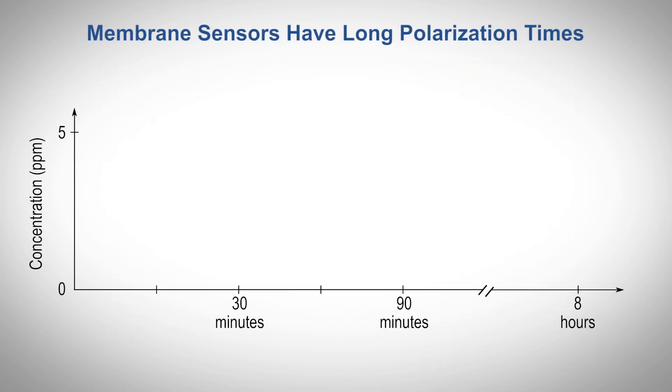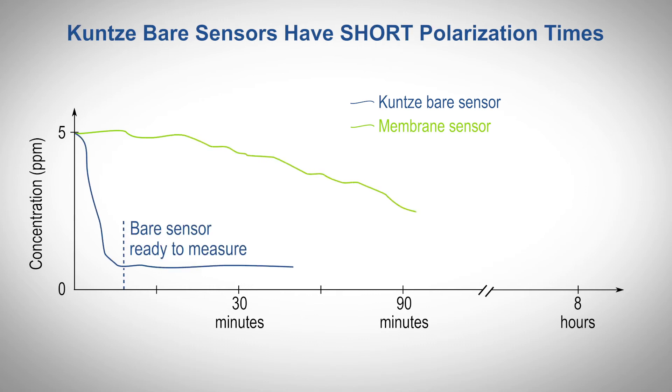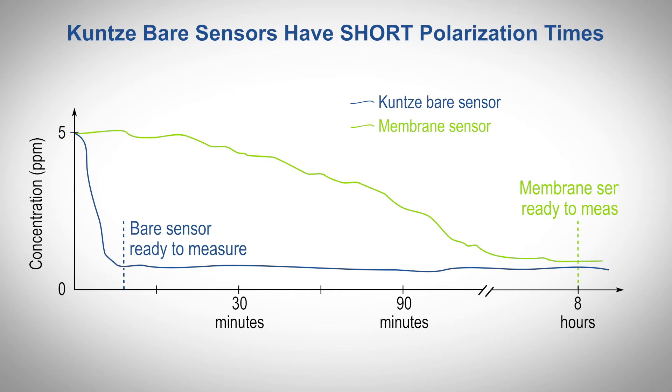Managing your process requires measurements to be fast and reliable. Upon installation, it can take a membrane sensor several hours to polarize and provide a measurement. Kuntze's bare sensors rapidly polarize, allowing sensors to be manually cleaned, installed, calibrated, and measuring within 15-30 minutes of installation.